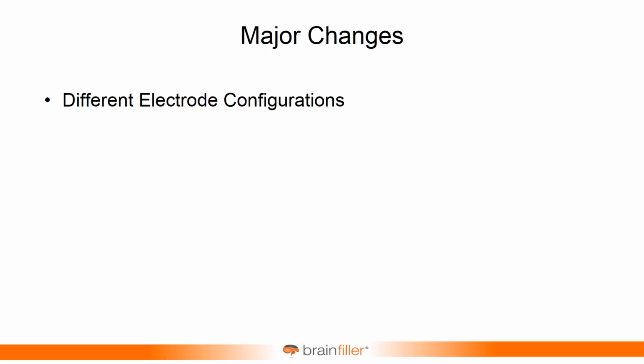The major changes. The first one is we have what are called different electrode configurations. I have some diagrams, and I'll explain this a little bit more in a few moments. The original 2002 tests were based on 3 electrodes in a vertical configuration. Basically, they were oriented down. And so what would happen was the energy would shoot away from the source down to the end of the electrodes, and it'd just come off the ends. That was fine. It was very successful. We got good equations out of it. Again, it was the first of its kind back in the day.